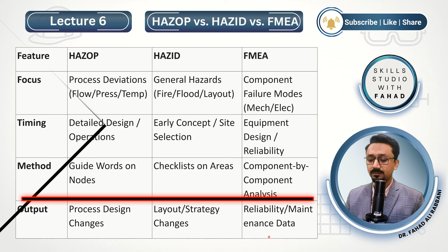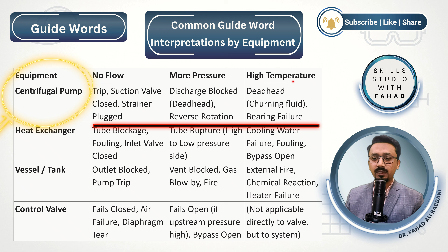For example, centrifugal pump, no flow: it shows tripping, suction valve closed or strainer plugged. More pressure: discharge blockage, deadhead has been created, or reverse rotation. It can also show a high temperature. This also represents a deadhead or bearing failure. For heat exchanger, no flow means tube blockage, fouling, inlet valve closed. More pressure means tube rupture, high to low pressure side. High temperature means cooling water failure, fouling, bypass open.